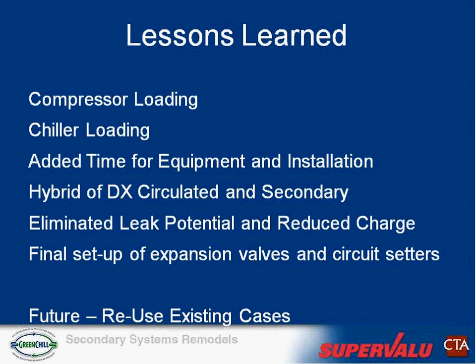What we learned is we can have a hybrid of a DX system and a secondary system. We did that where some coolers stayed on the DX system because the coils had just been recently replaced or were in good shape, so we couldn't gain by changing out those coils. They ran off the same rack that was chilling the alcohol system. We learned you could do your change out in phases, because you only plan on changing out so many cases, but as you build your pump system and your piping system, the refrigerant capacity is going to be there because it's just going to switch from doing it as direct expansion to doing it as secondary. So it's something that could be staged even outside of the project.